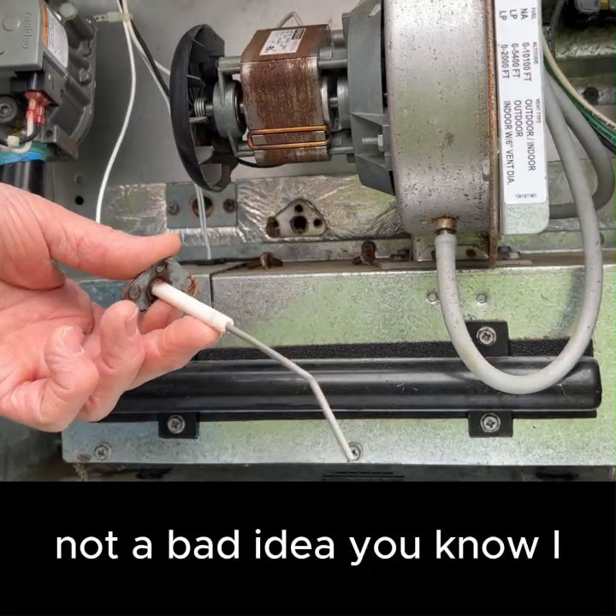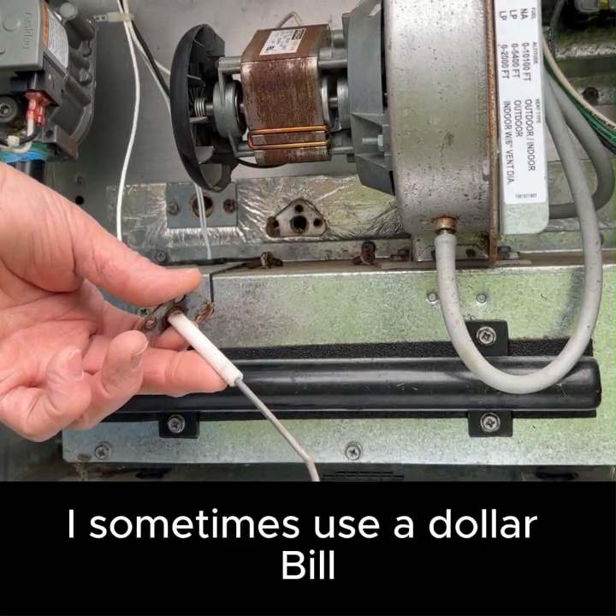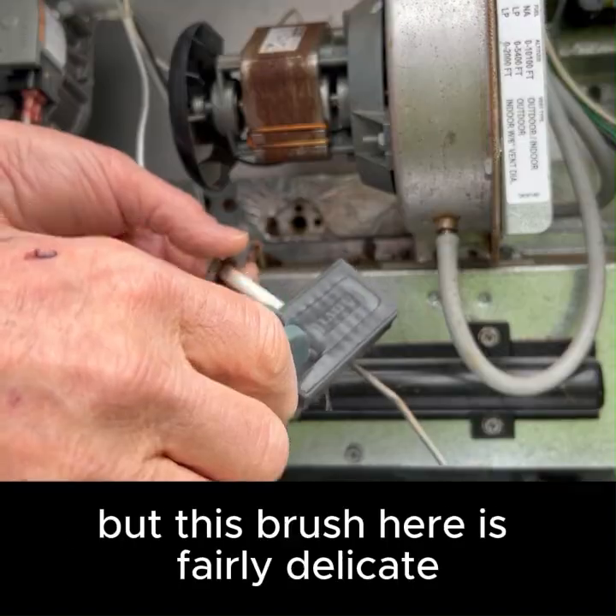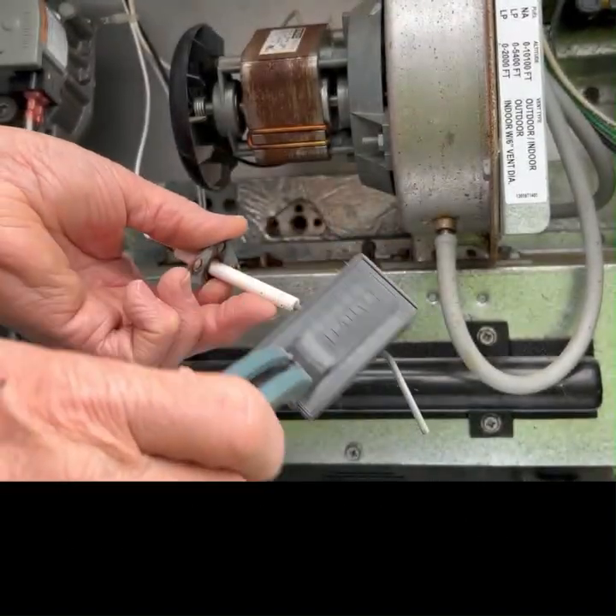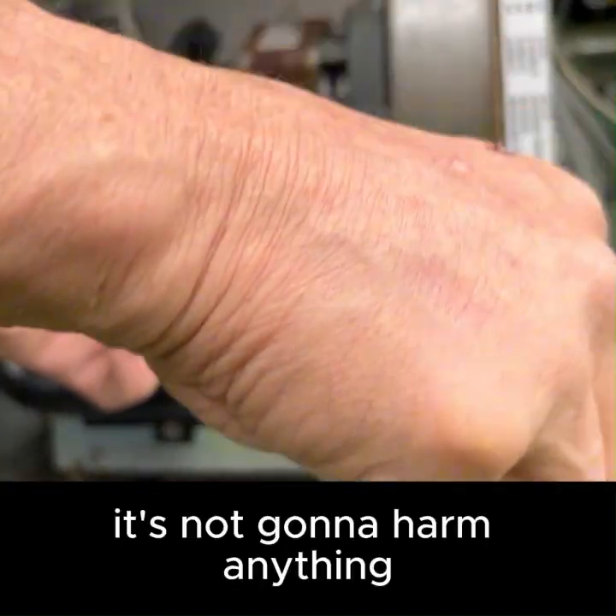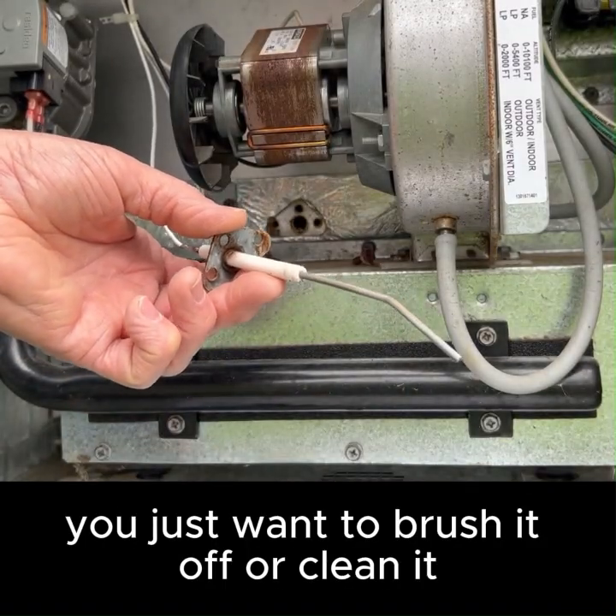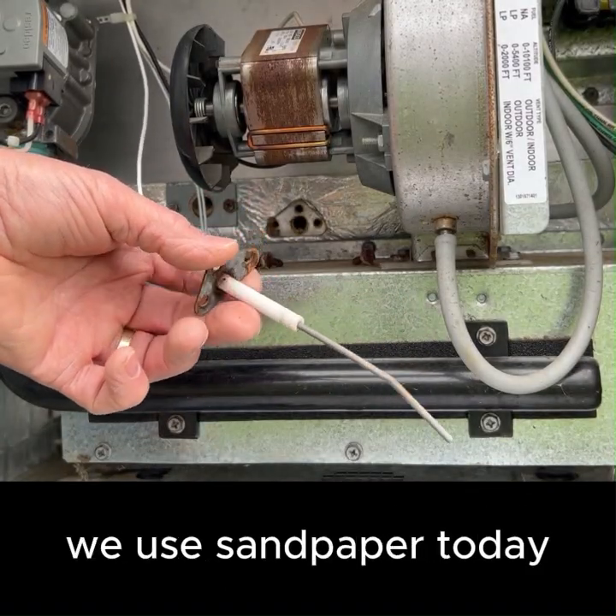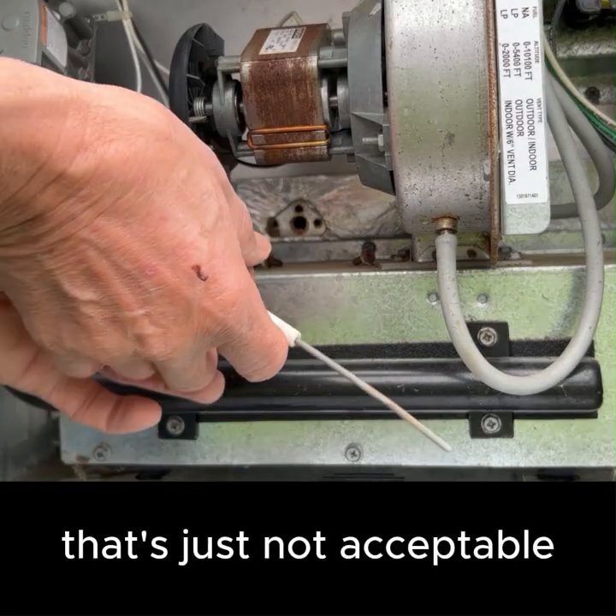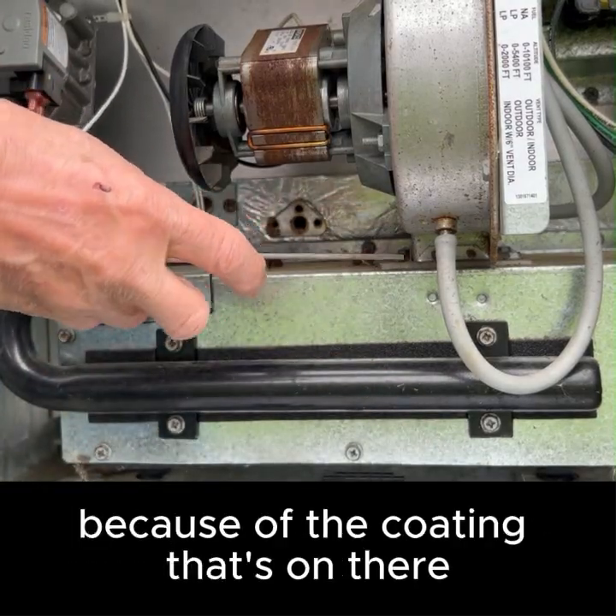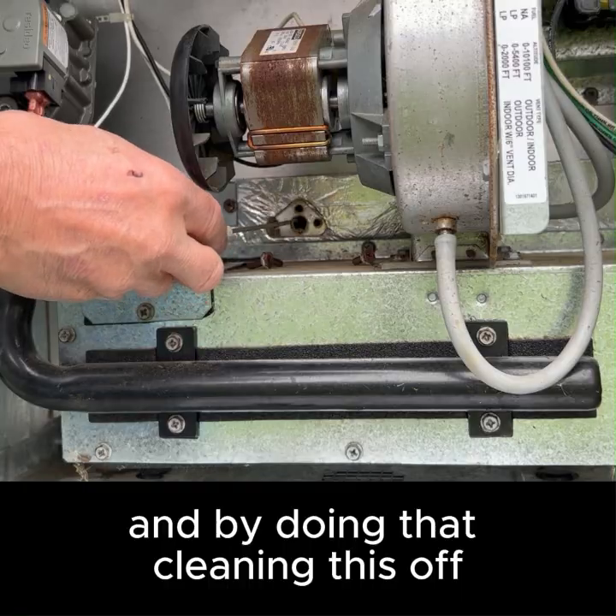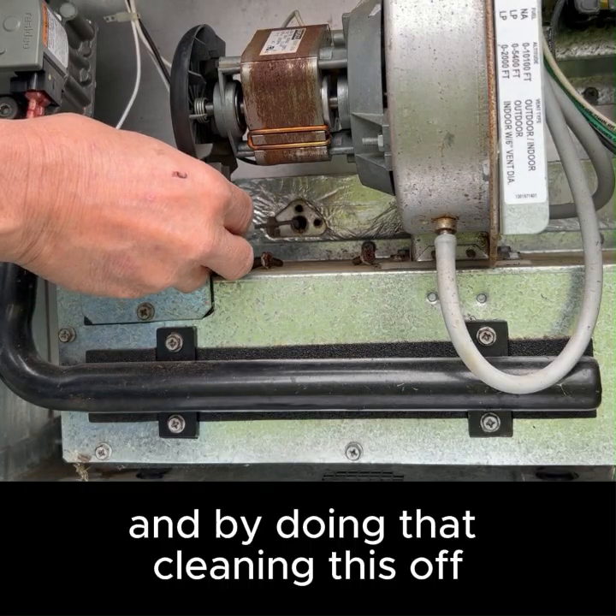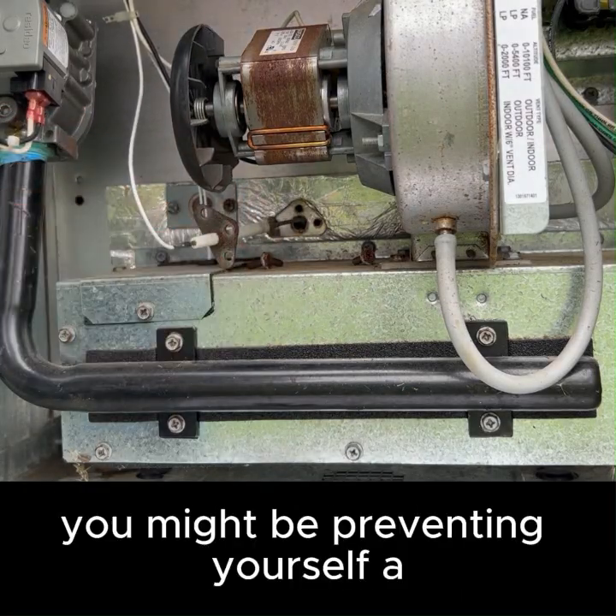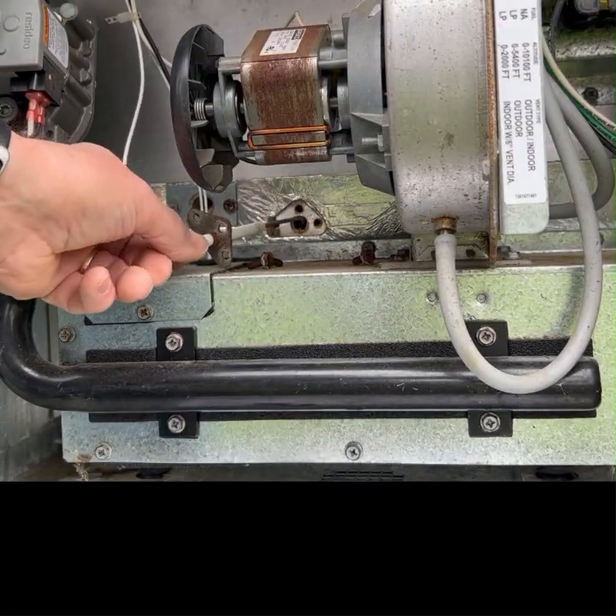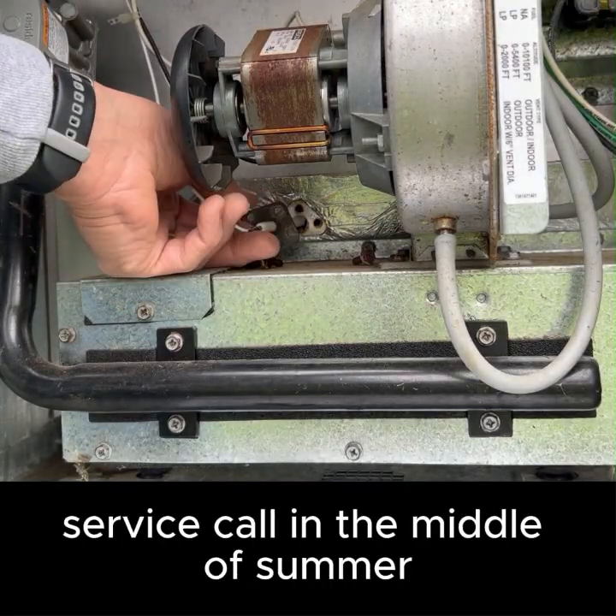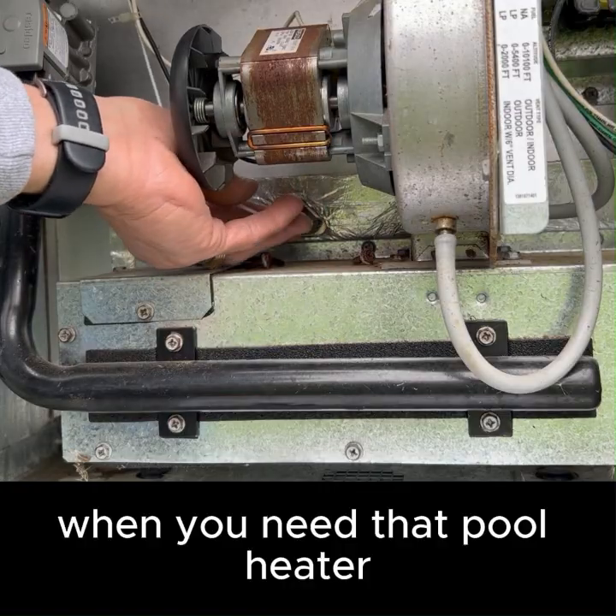Not a bad idea. I sometimes use a dollar bill, but this brush here is fairly delicate. It's not going to harm anything. You just want to brush it off or clean it. Like I said, in the old days we used sandpaper. Today that's just not acceptable because of the coating that's on there. And by cleaning this off, you might be preventing yourself a service call in the middle of summer when you need that pool heater.